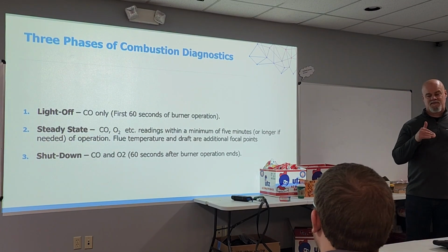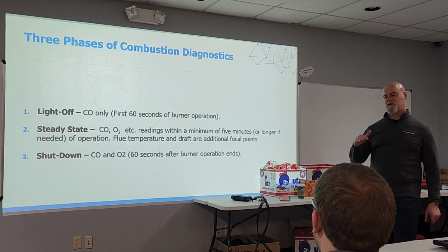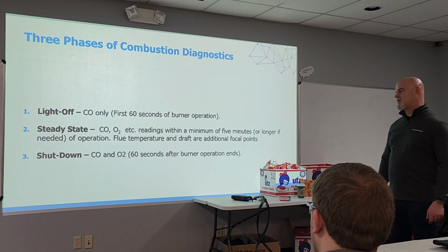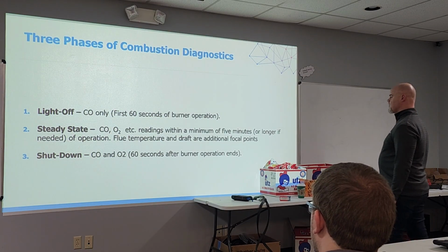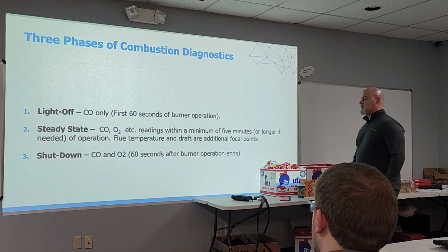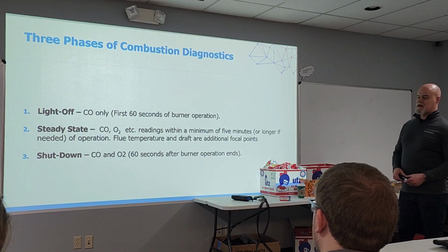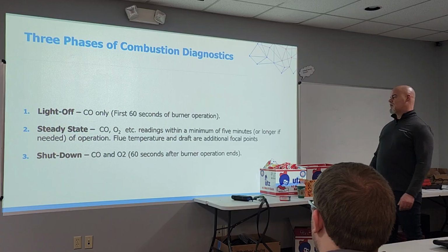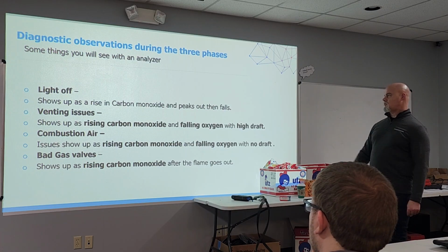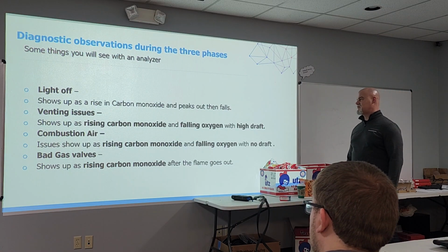You're always taking your draft at steady state because that's the sweet spot in the system's running capabilities, when the flue is nice and warmed up and everything's proper, or should be proper. And then shutdown: you're going to focus on CO and O2, and that is 60 seconds after the burner operation ends.